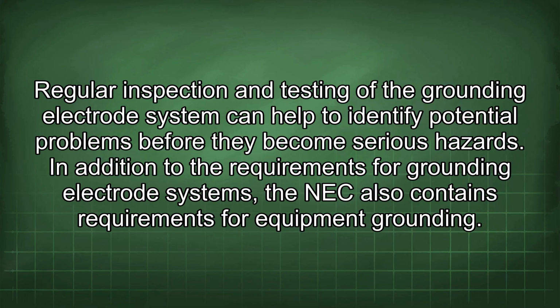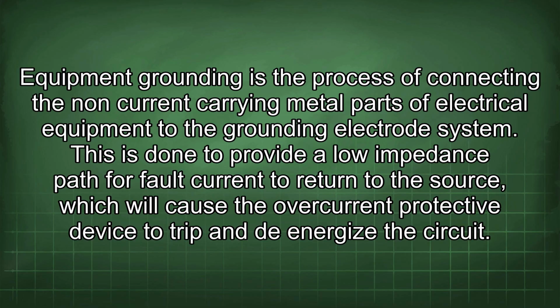In addition to the requirements for grounding electrode systems, the NEC also contains requirements for equipment grounding. Equipment grounding is the process of connecting the non-current carrying metal parts of electrical equipment to the grounding electrode system. This is done to provide a low impedance path for fault current to return to the source, which will cause the overcurrent protective device to trip and de-energize the circuit.